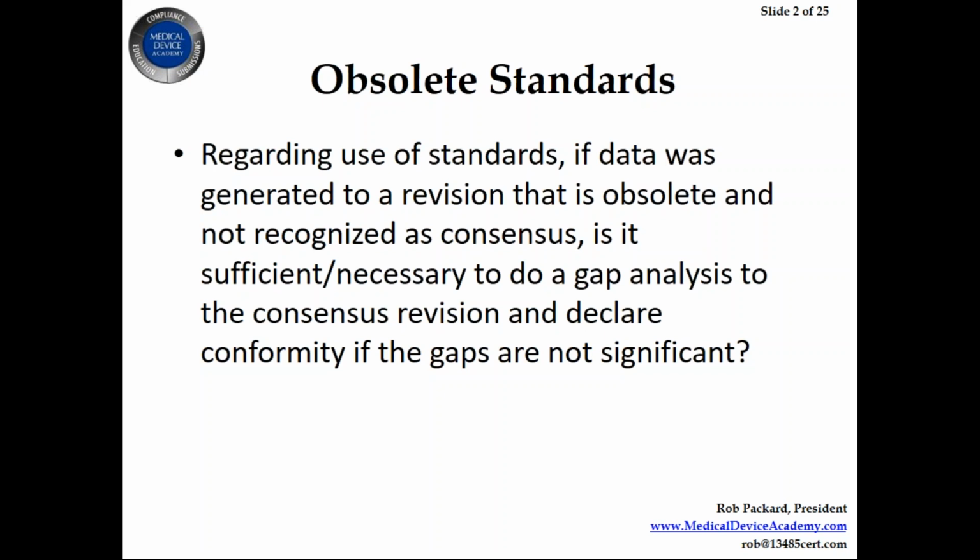And specifically, one of the common ones out there is sterilization. They didn't change the sterilization standards all that long ago, so I actually had a client early in this year. They had done the testing last year. This standard had changed. All the testing was done to an old version, and their testing didn't meet the new version's requirements, and so therefore they had to redo their entire sterilization validation testing.